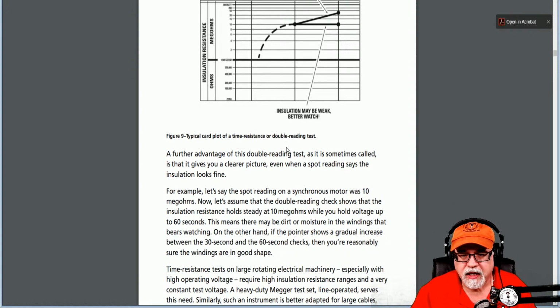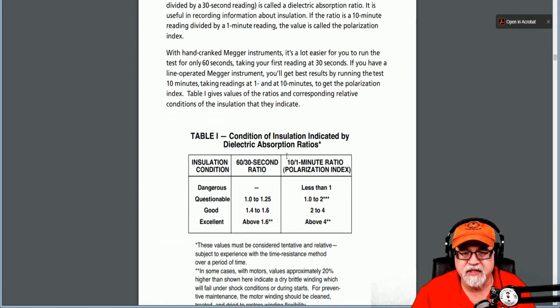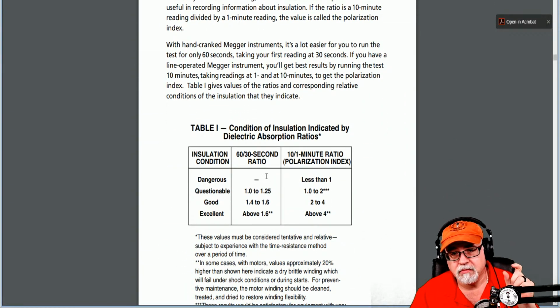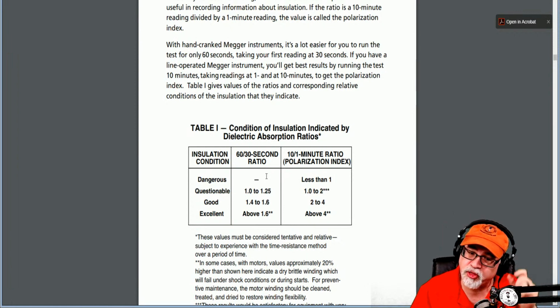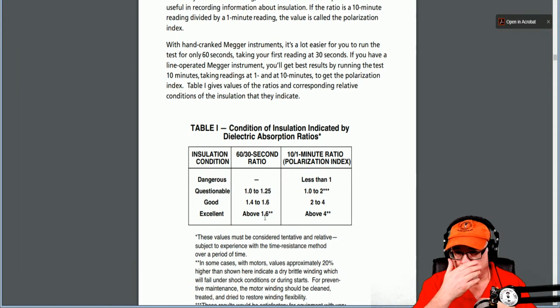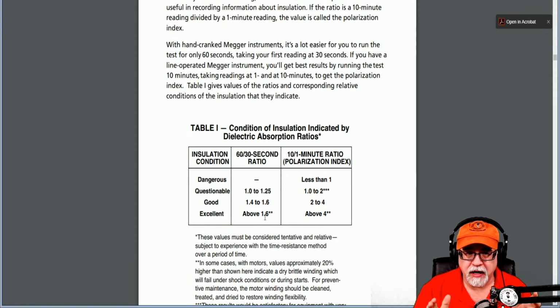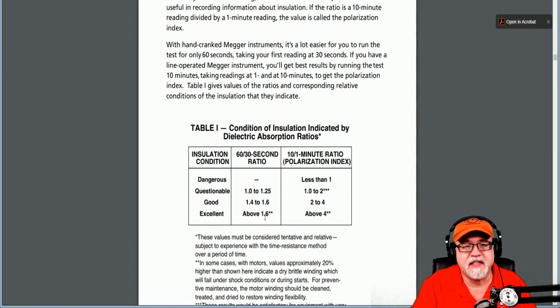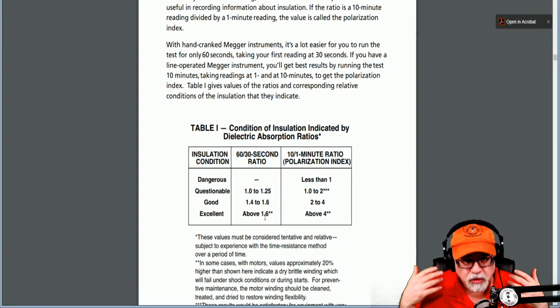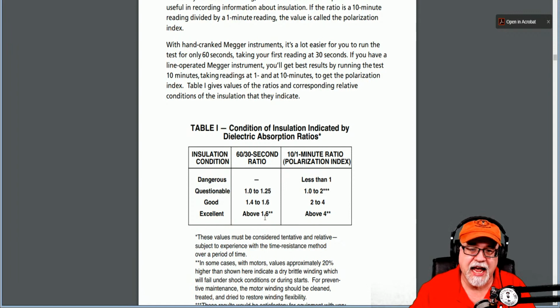And what you're going to do is you're literally going to take that 60-second value and you're going to divide it by the 30-second value. And that's going to give you a ratio. Now, if your ratio is 1.0 or greater, when you're dealing with wire and cable, not a problem, okay? Now, if it falls below 1.0, then it just means further evaluation. It means that immediately we're going to jump to the 10 and 1, since you're already taking those values anyway.